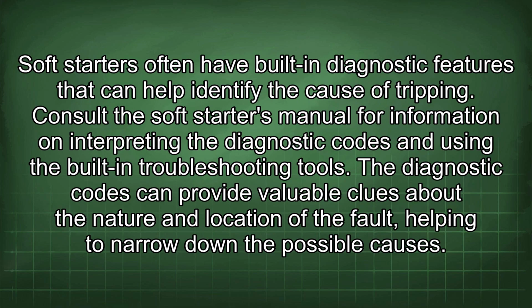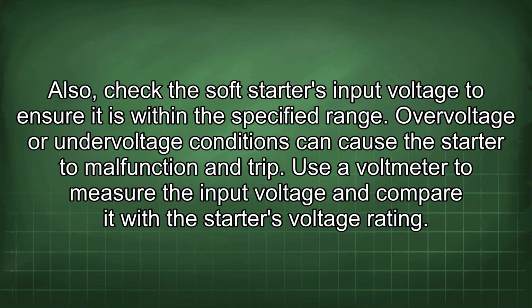Soft starters often have built-in diagnostic features that can help identify the cause of tripping. Consult the soft starter's manual for information on interpreting the diagnostic codes and using the built-in troubleshooting tools. The diagnostic codes can provide valuable clues about the nature and location of the fault, helping to narrow down the possible causes. Also, check the soft starter's input voltage to ensure it is within the specified range.